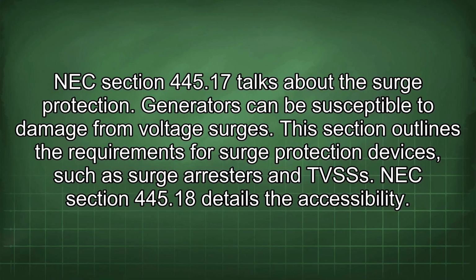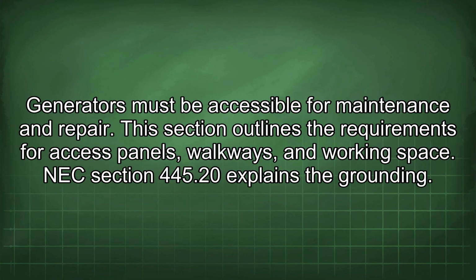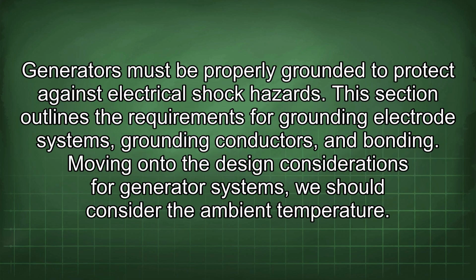NEC Section 445.18 details the accessibility. Generators must be accessible for maintenance and repair. This section outlines the requirements for access panels, walkways, and working space. NEC Section 445.20 explains the grounding. Generators must be properly grounded to protect against electrical shock hazards. This section outlines the requirements for grounding electrode systems, grounding conductors, and bonding.